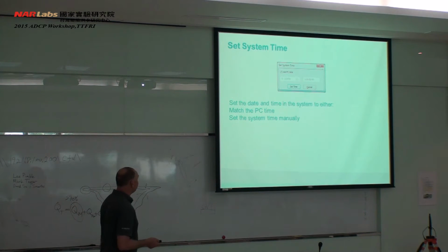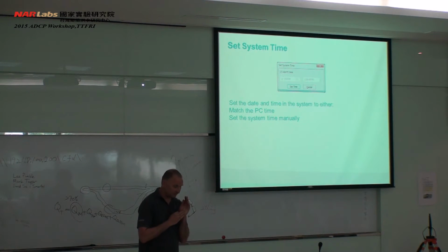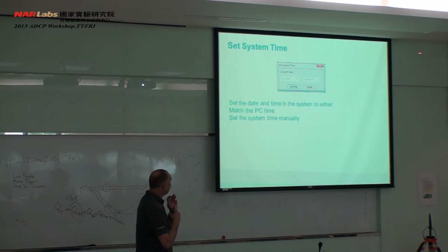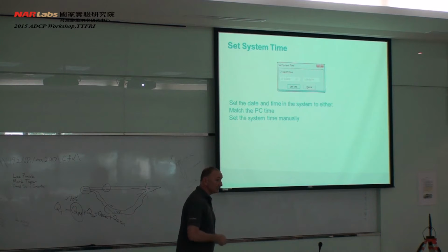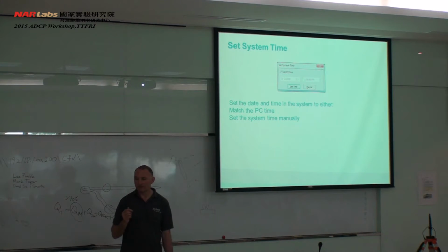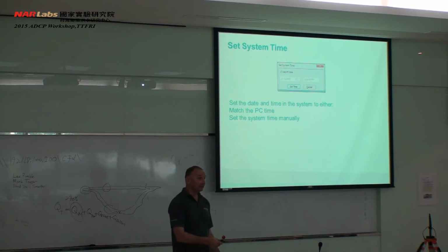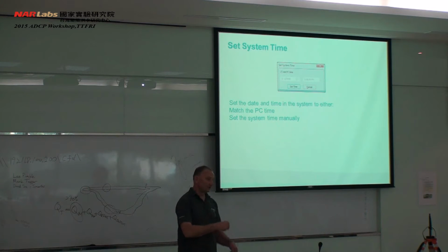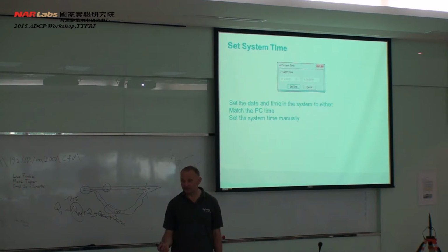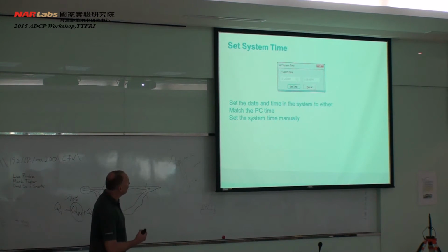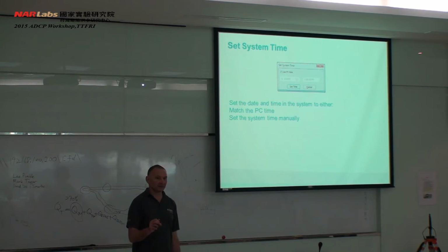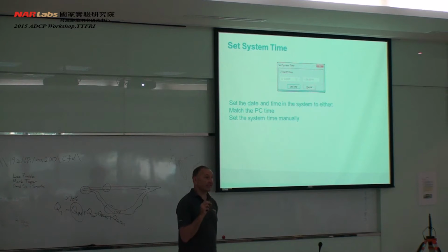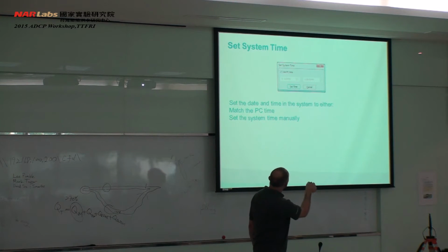Set system time. A couple of things to remember with setting the system time. There is the box to check for use PC time. Certainly in the UK, we're not allowed to set the instrument to use PC time. We always have to set it to actual clock time and to GMT. So all of our measurements in the UK are made to GMT, which you wouldn't normally get from a PC. The instrument records its data at whatever time you have set here.